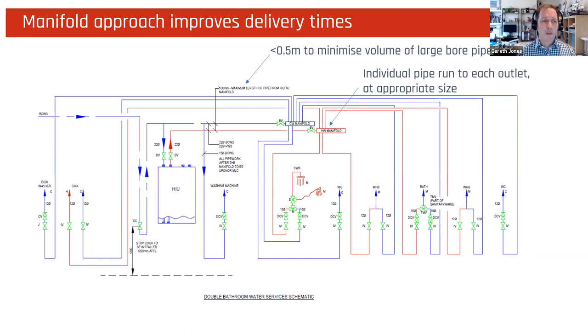On the manifold approach, again, I mentioned it before, we try minimizing, so less than half a meter between the HIU and the hot water manifold, to minimize the volume of large bore pipework that you have to draw down each time to clear, and then individual pipe runs.